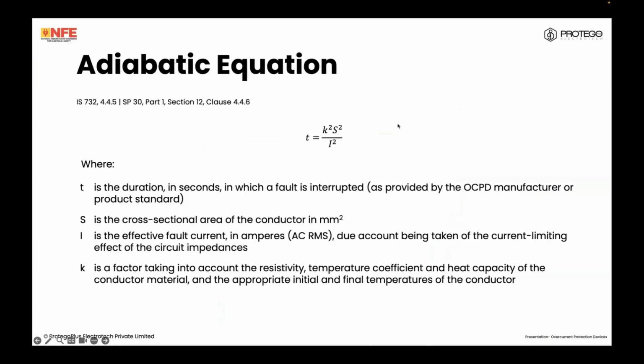Okay, we look at IS 732 clause 4.4.5 and clause 4.4.6 of section 12 part 1 of the National Electrical Code. It tells us that t shall be equal to k squared S squared upon I squared. This t is essentially the duration in seconds in which a fault has to be interrupted as provided by the OCPD manufacturer or the product standard. So this is basically saying that for a given fault and a given cable, this is the maximum time that the fault has to be interrupted in. If the breaker or the OCPD disconnects in a time greater than this, there will be damage to the cable. S is the cross-sectional area of the conductor in square millimeters. I is the fault current in root mean square value, that's the RMS value, account being taken of the current limiting effect.